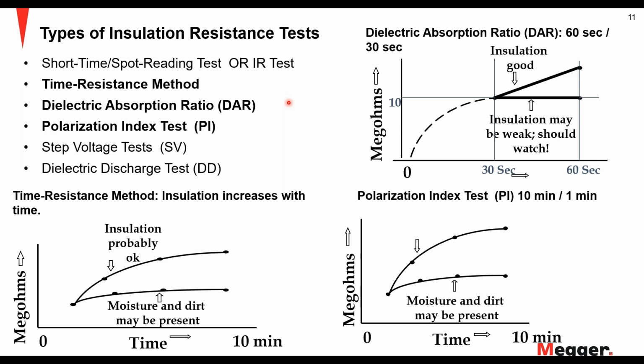Then you have your time resistance method. That is, you are supplying the voltage for X amount of time. That X amount can be decided by the user. It's 30 seconds, 60 seconds, 1 minute, 2 minute, whatever. So that is time resistance test. You're basically defining that I want to test it for X amount of time.